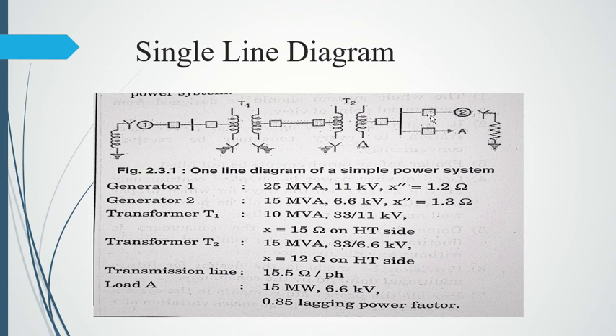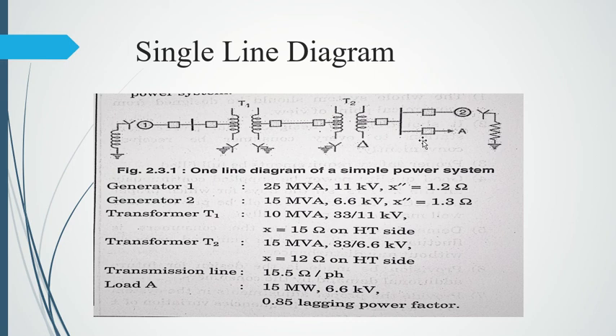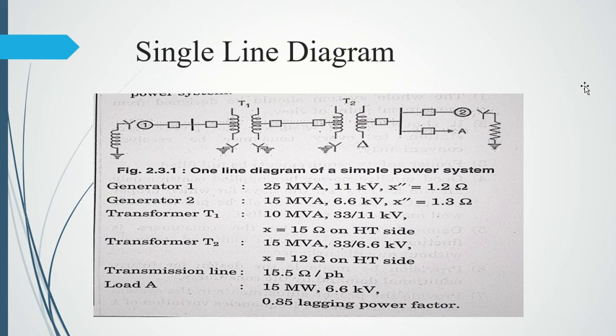T2's primary side is connected with a grounded star connection and its secondary side has a delta connection. From the delta secondary, the line goes to another circuit breaker, then to a feeder — a vertical bus — that distributes power to two loads. One path connects via circuit breaker to a second generator (15 MVA, 6.6 kV, reactance 1.3 ohms, with grounded star and resistive element), and the other connects to Load A: 15 MW, 6.6 kV, 0.85 lagging power factor.